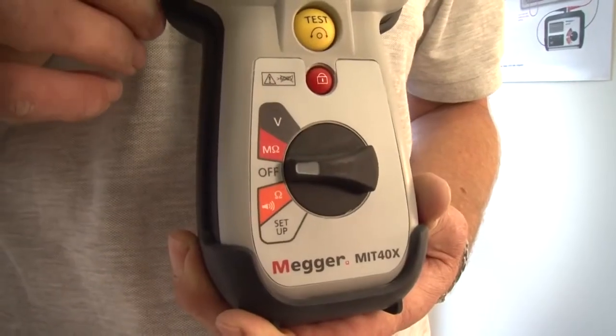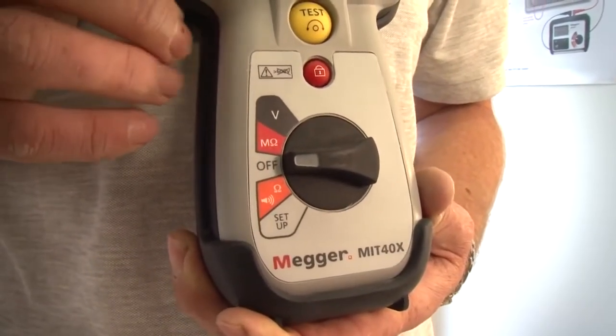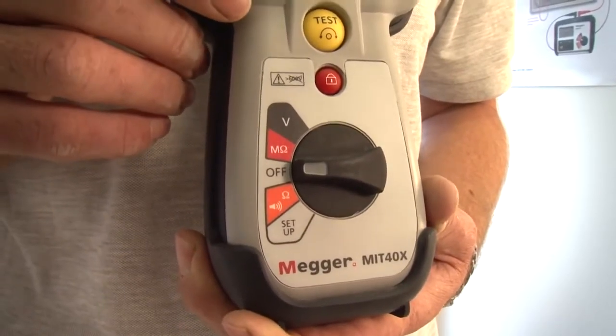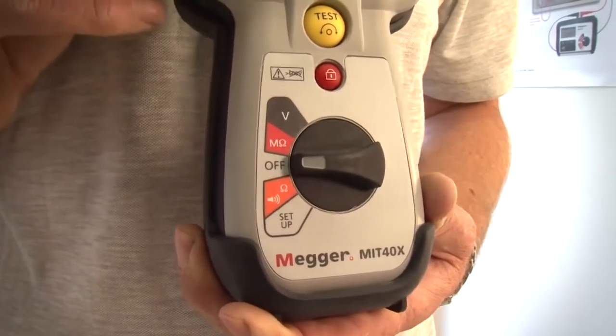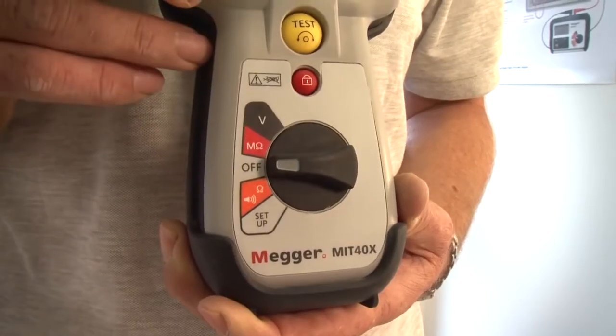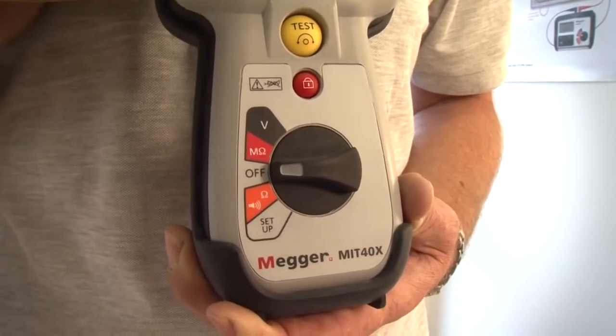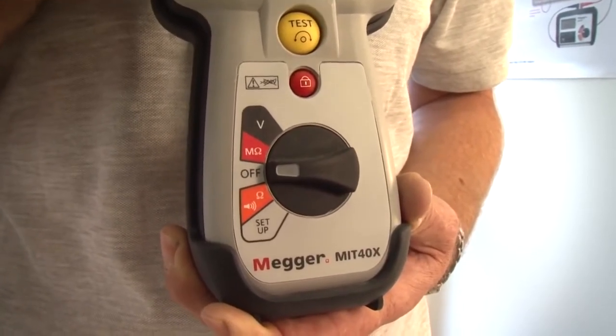The final product to mention is the MIT40X. This is a special application insulation tester and features a single insulation test range with a variable test voltage. The test voltage can be set anywhere between 10 volts and 100 volts with 1 volt increments. It has insulation leakage current display, as well as the insulation resistance value and a continuity measurement range up to 100 ohms. As with all of the products, it has true RMS AC and DC voltage measurement facility as well.